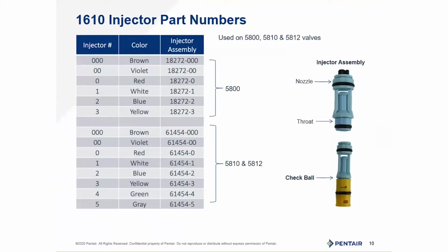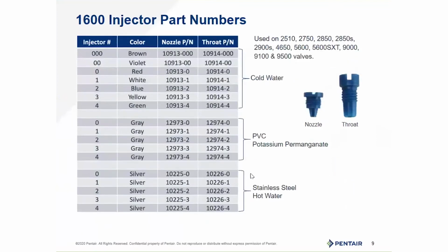Earlier today, we had the question, does temperature affect venturis? Not particularly, because we're reducing the water flow so much through this nozzle that temperature doesn't play a real role here, unless you're overcoming the materials of construction, where you really need to upgrade from plastic or PVC to a stainless steel injector throat. That's where you're going to see issues and you're going to want to change materials. But in the larger units, it's not typically a problem.